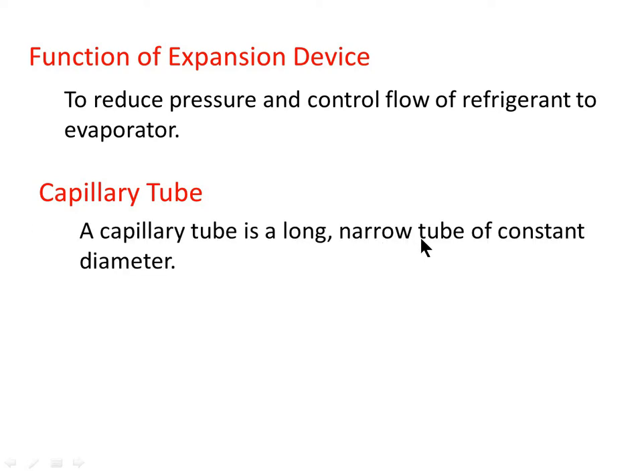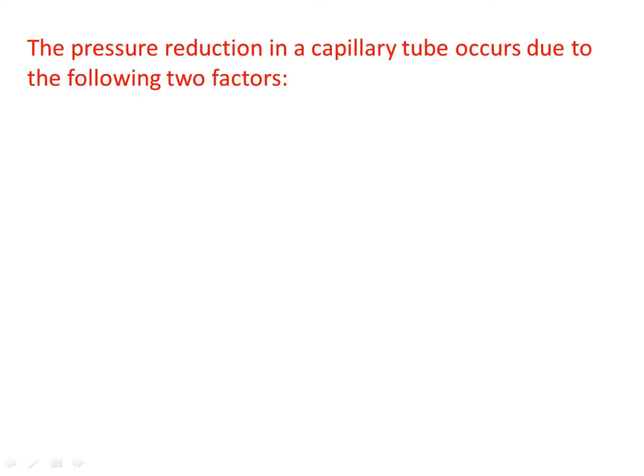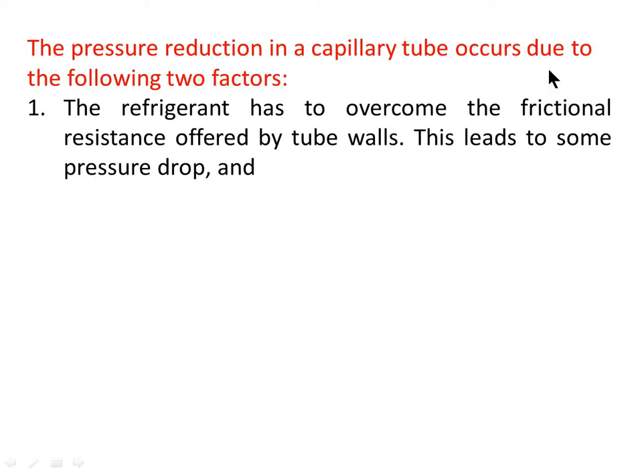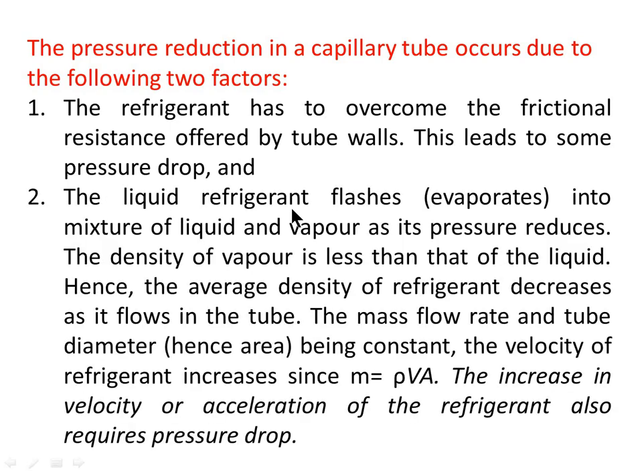A capillary tube is a long narrow tube of constant diameter. Pressure reduction in a capillary tube occurs due to two factors. First, the refrigerant must overcome the frictional resistance offered by the tube walls, causing a pressure drop. Second, the liquid refrigerant flashes into a mixture of liquid and vapor as its pressure reduces. Since vapor density is less than liquid density, average density decreases as refrigerant flows through the tube. With mass flow rate and diameter being constant, velocity increases, and since m = ρvA, this acceleration also requires a pressure drop.